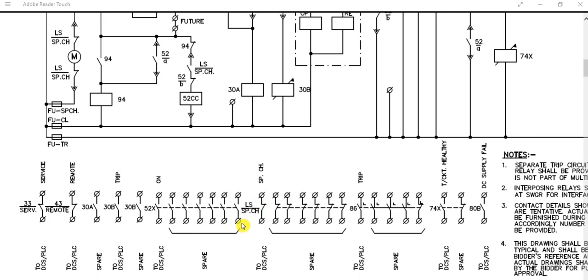This is the spring charge limit switch contact — the motor spring charge limit switch contact — and it is also going to DCS. Next, 86 is the main lockout relay. This trip signal is going to DCS or PLC, and the remaining contacts are spare.